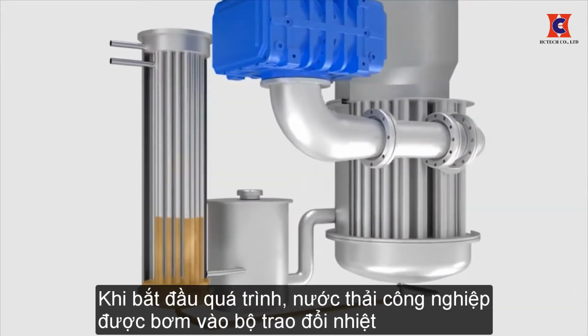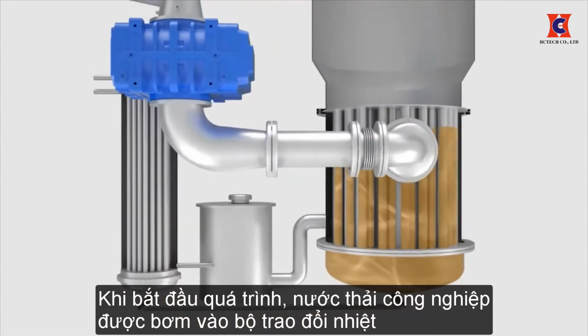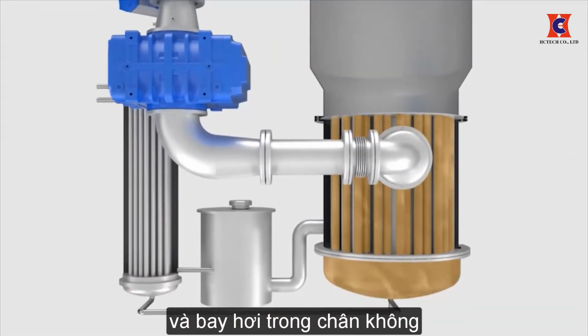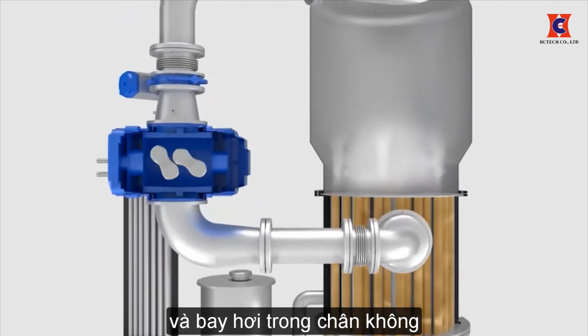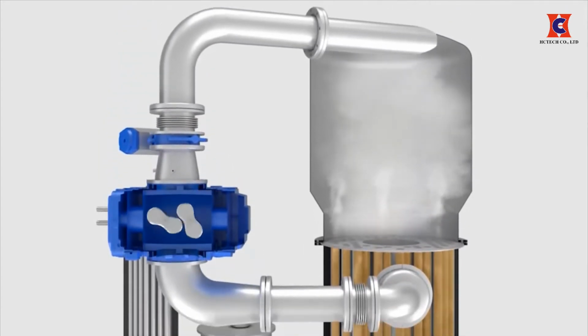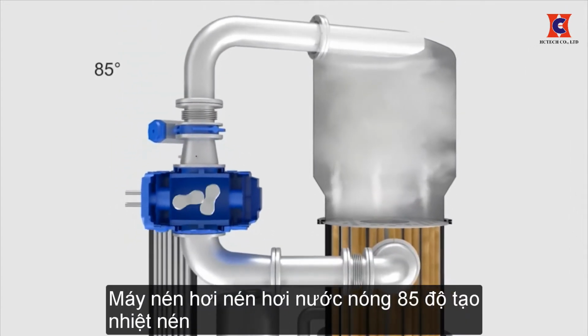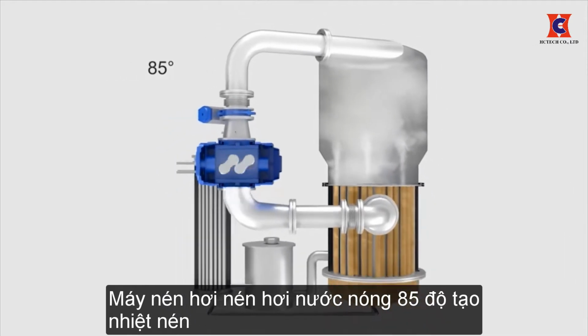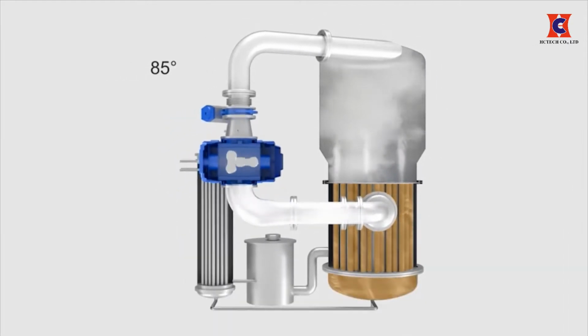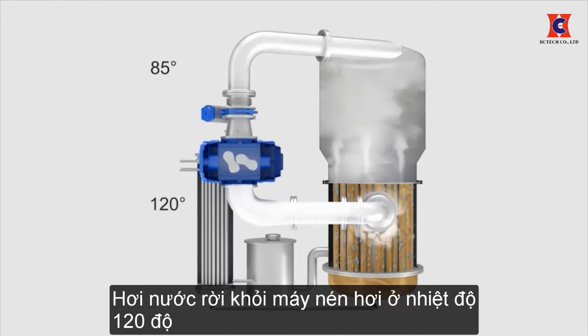At the beginning of the process, industrial wastewater is pumped into the heat exchanger and evaporated under vacuum. The vapor compressor compresses the 85-degree hot steam, creating compression heat. Steam leaves the vapor compressor at a temperature of 120 degrees.